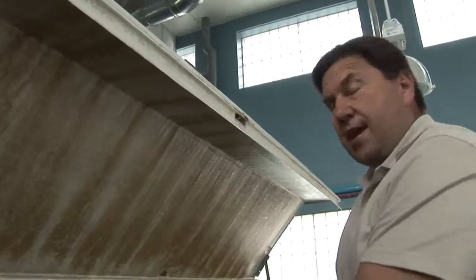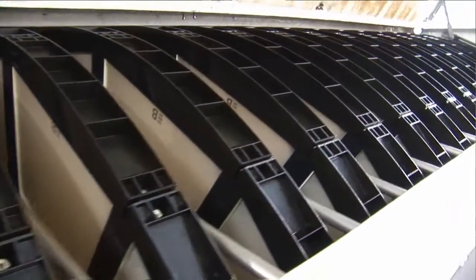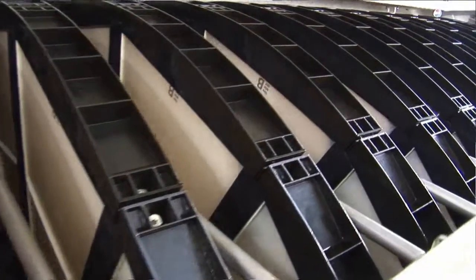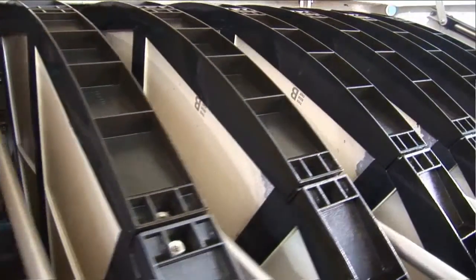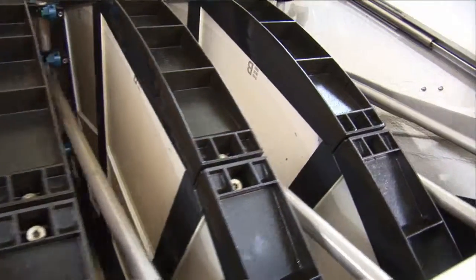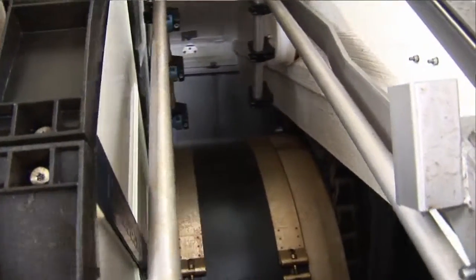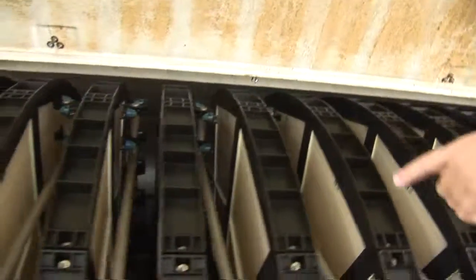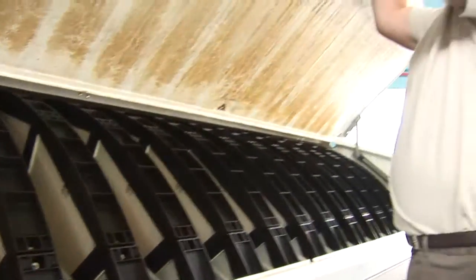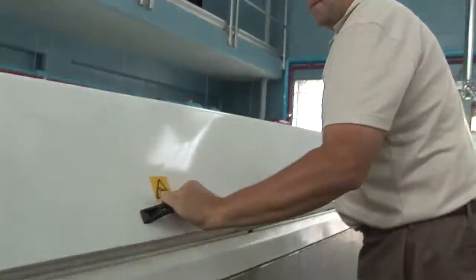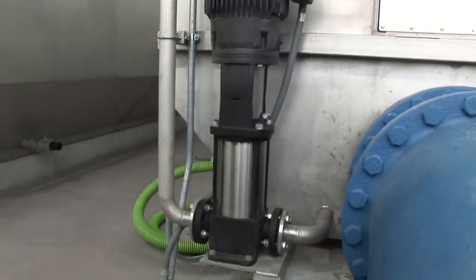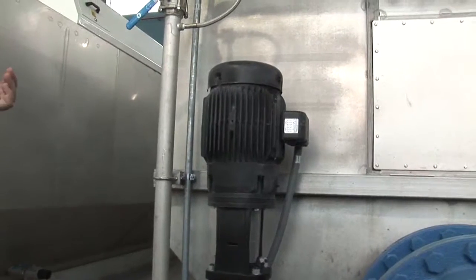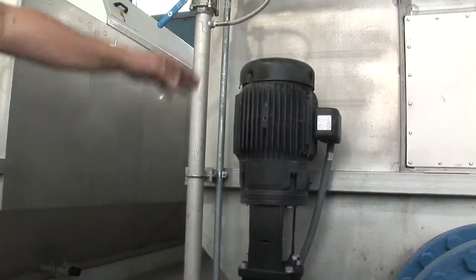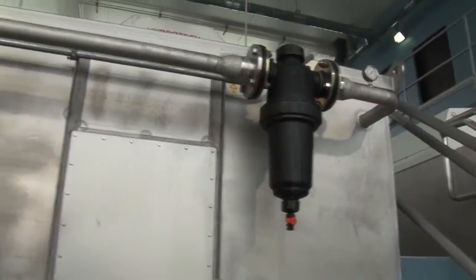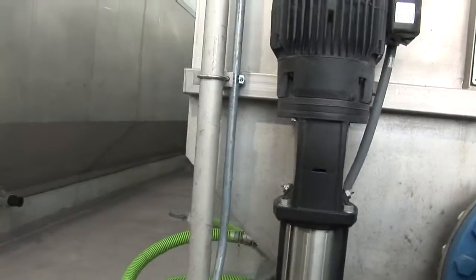This is one of our filters. The flow comes in. It goes through the center of the disc. The flow goes through the membranes from the inside out and then transfers down to the effluent of the tank, and then it goes out to our UV system. We have 14 panels through the disc, and we have 15 disc units per filter system. Each filter is a self-contained unit, so if we took one filter out of line, all the other filters would continue to operate. Each filter has its own backwash pump, a filter screening for the backwash, and its own effluent and influent valves.